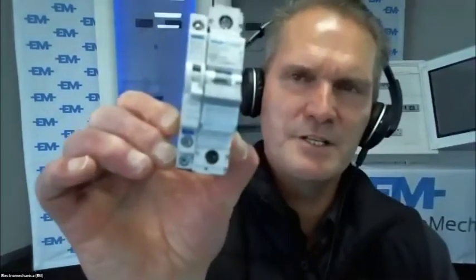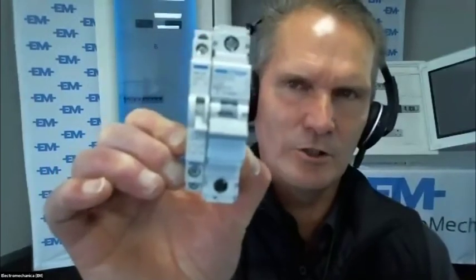the products. So if you look there, hopefully you can see it, this is the NFN product. Inside of the product, there's a small clip here for you to fit in the auxiliaries. So what you do is you just remove it. You've got a hole on your product then. You can then take the, as I said, the auxiliary. You can, let me try and do it this way around. You can then just clip it onto the product. At the bottom, there's a clip that you just open and it clips in. So now you've got a miniature circuit breaker with a normally open close contact on that.